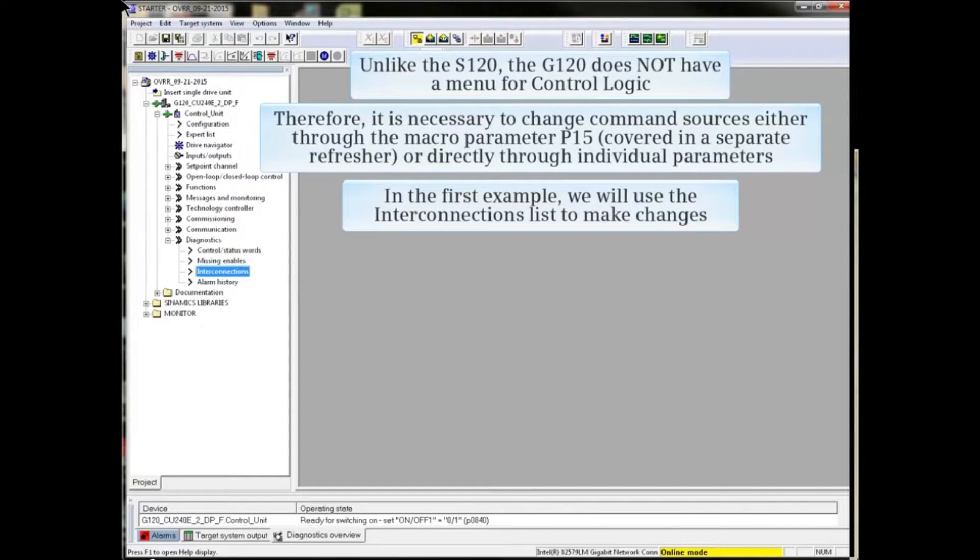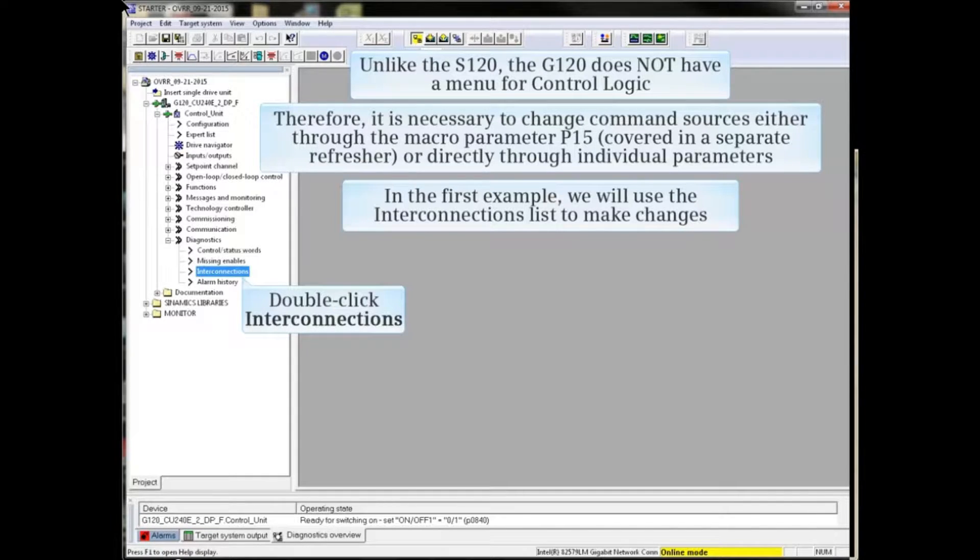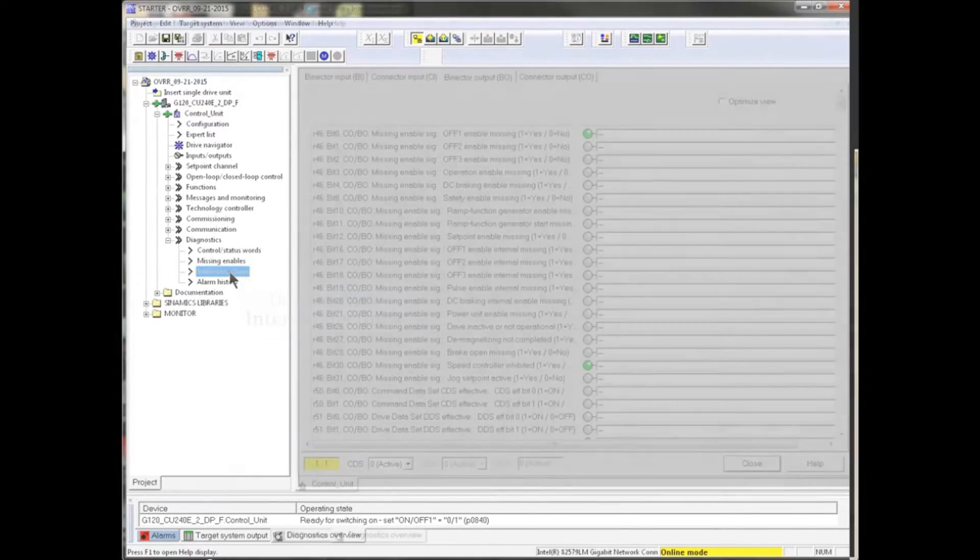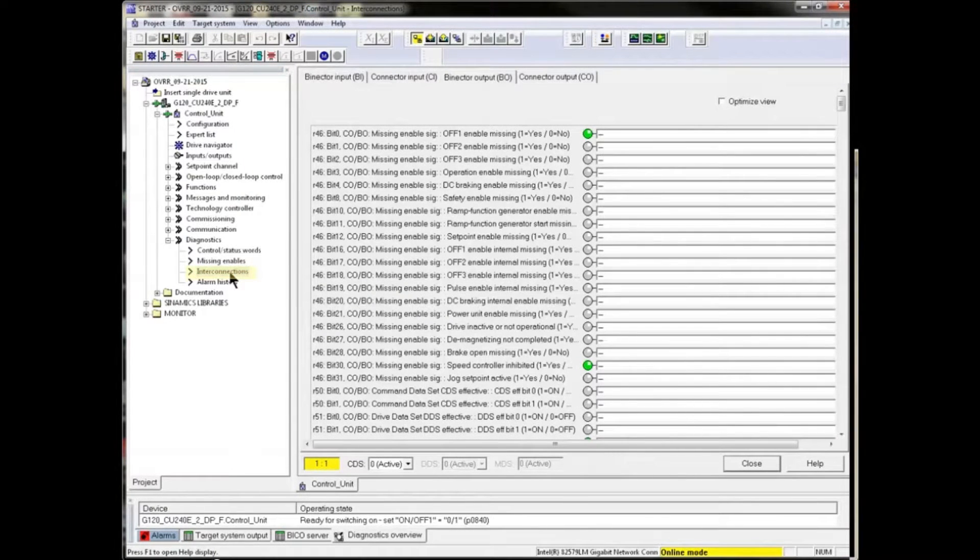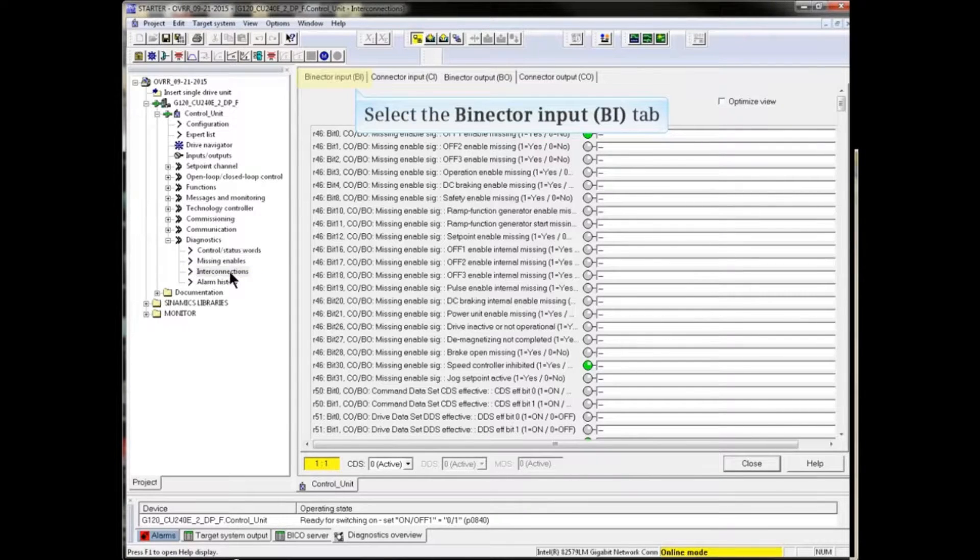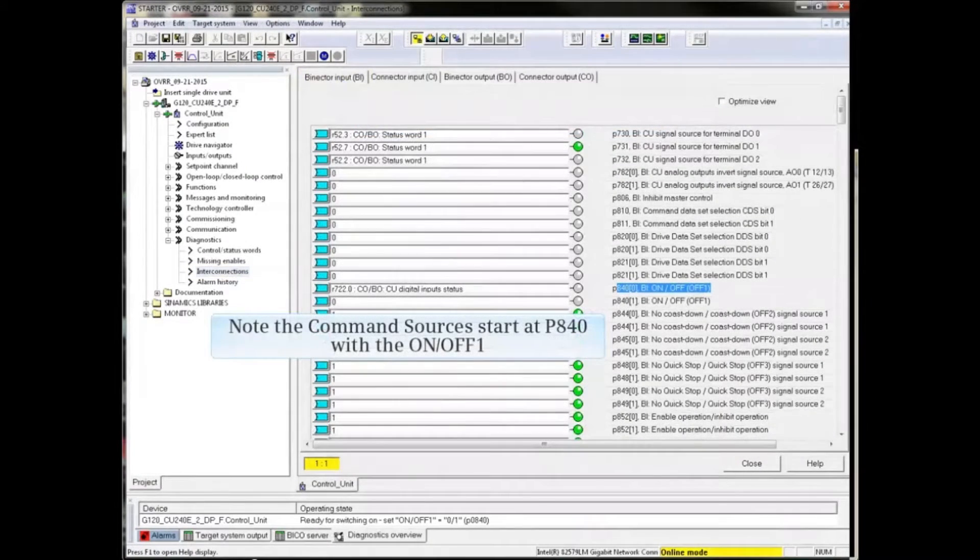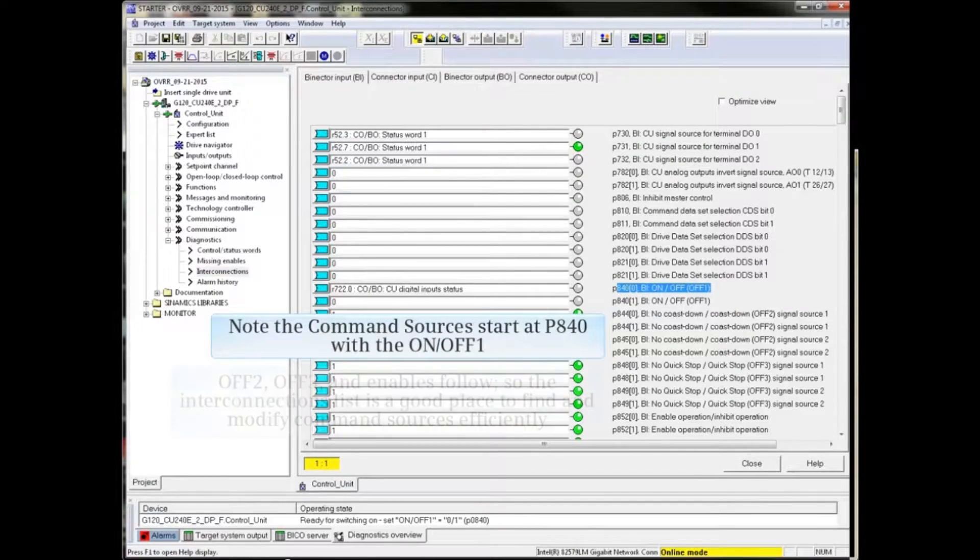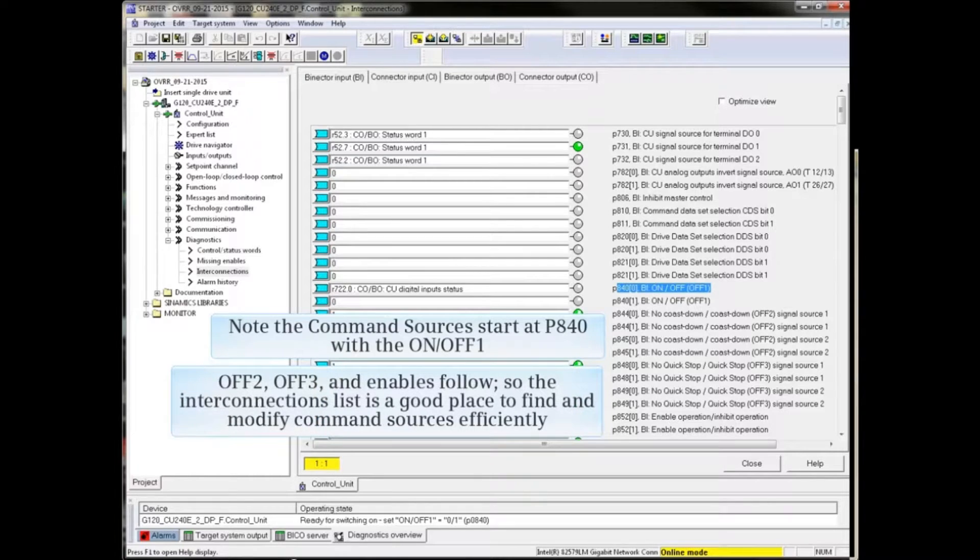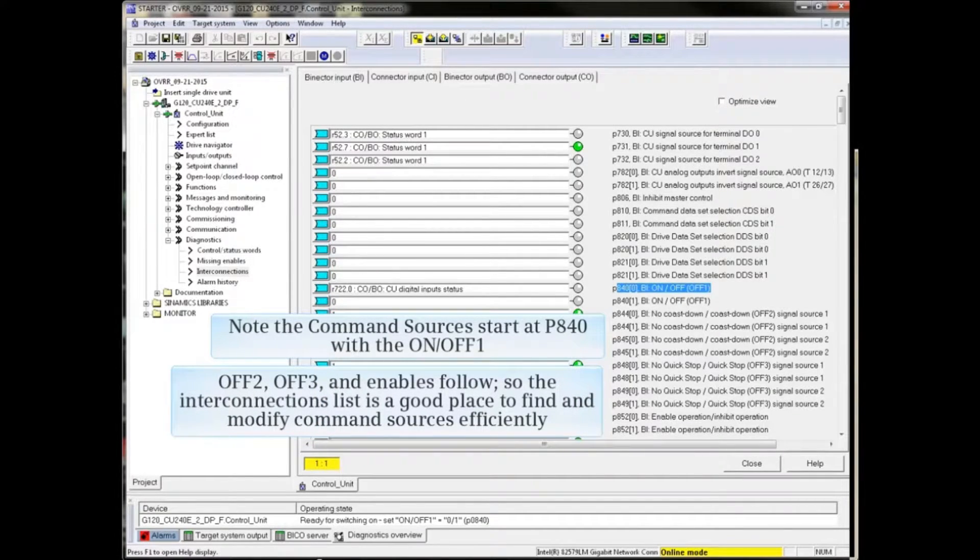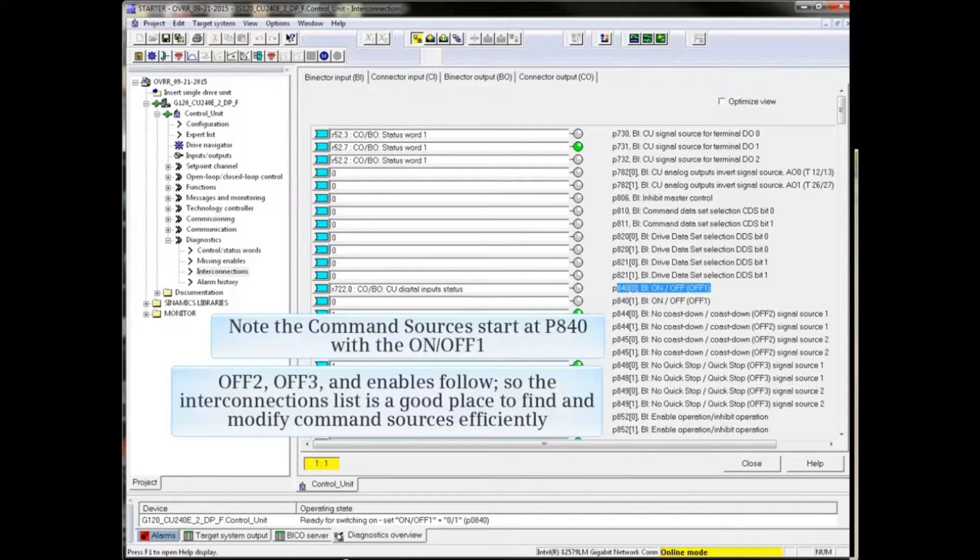In the first example, we will use the interconnection list to make changes. Double-click interconnections from the project tree under Diagnostics. In the interconnections list, click the Binector Input tab. Note that the command sources start with P840, the ON/OFF1, OFF2, OFF3, and Enables follows, so the interconnections list is a good place to find and modify command sources efficiently.